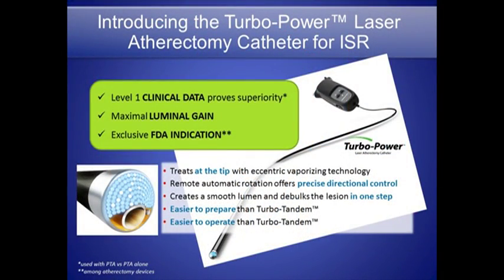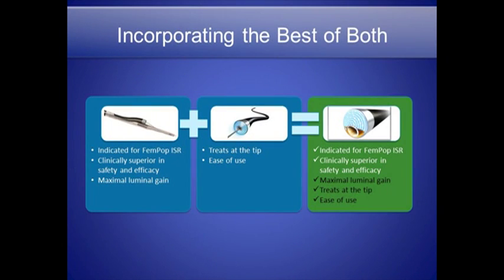We've worked with companies to develop new products over the years to better treat this problem. This was one of our collaborative projects to develop a product that would allow us to better clean out stents that had been blocked up by material that grows inside a placed stent. This product is called the Turbo Power catheter. I brought some slides to show you. The difference from standard laser devices is that this laser fiber has a wire lumen off to one side and a little motor that spins it back and forth, allowing us to clean out an artery much more effectively rather than just pushing it in one dimension. Compared with older technologies like the Turbo Booster on the left — which was a ramp, and we were also the first in the world to use that — the older device leaves dead space and doesn't make a perfectly round channel.